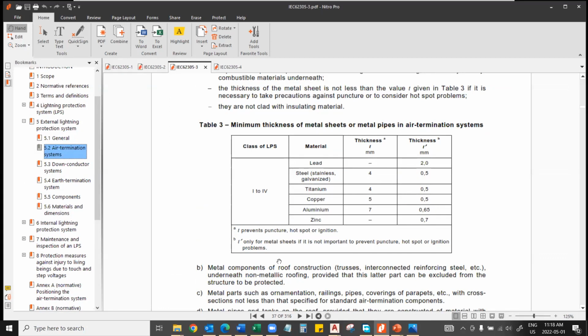Okay, so in order to prevent a puncture or a hotspot or ignition, you have to make sure these thicknesses are maintained. My gosh, it's like 4 millimeters, 7 millimeters. Consider the weight of the roof, it will impact, right? Because it's a lightning current, you need a minimum cross section to conduct it without causing sudden temperature rises, which can melt the spot of strike, which can cause punctures or even a hotspot, or can lead to ignition later on. If you have an ignition, it could be catastrophic, because the ignition in the roof will fall onto your stored items or pile of items, and then it can spread a fire as well.